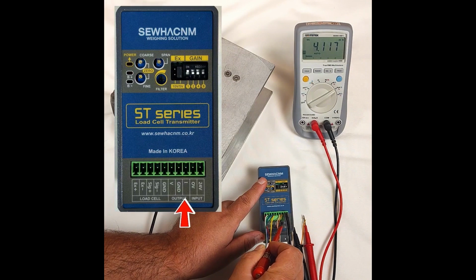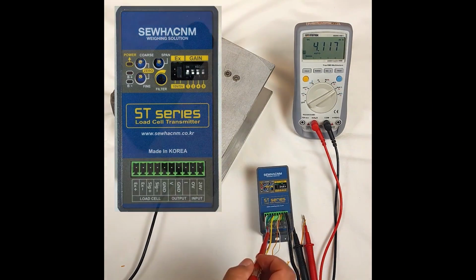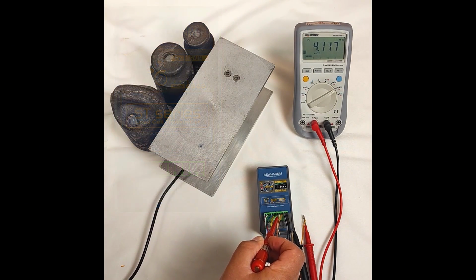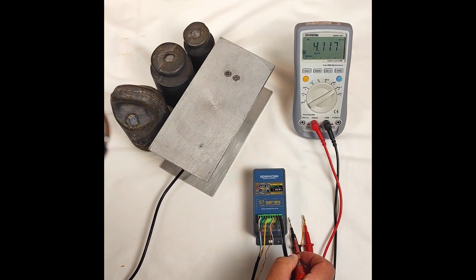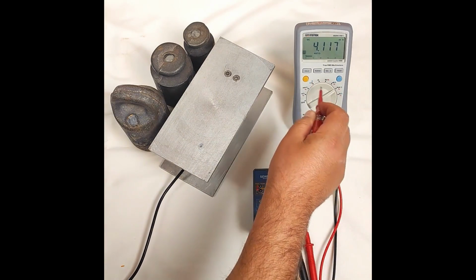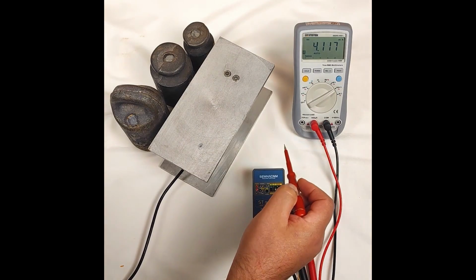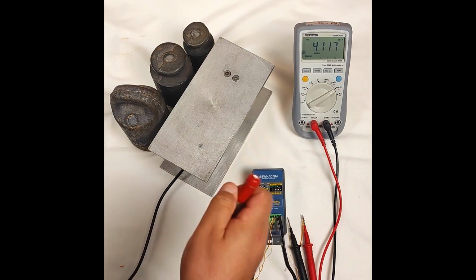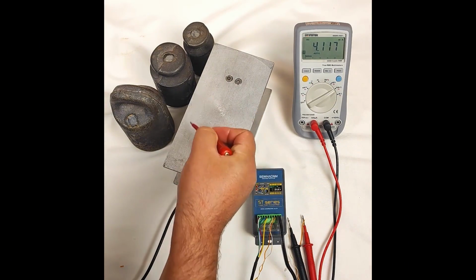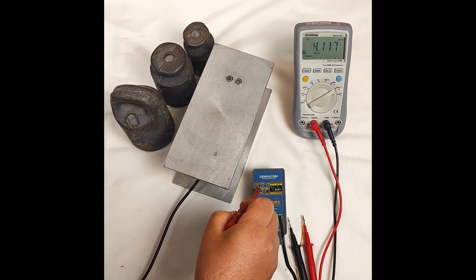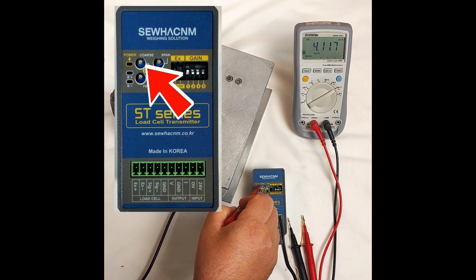After connecting the load cell, as you can see, we have an I terminal that gives us the current output, and a GND terminal, which is actually the ground. So the output we get from our transmitter comes from the I and GND terminals. I is positive and GND is negative. We've connected two wires to these terminals and attached them to the corresponding wires of the multimeter. We've set the multimeter to the milliamp mode, and currently the load cell is unloaded with no weight on it.